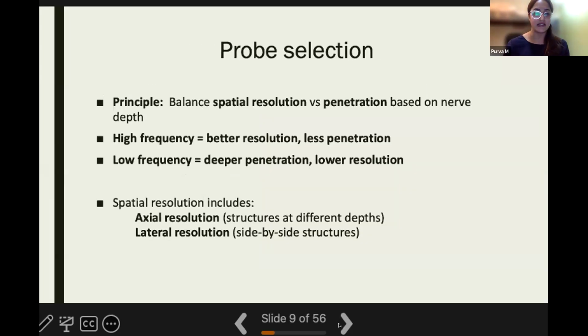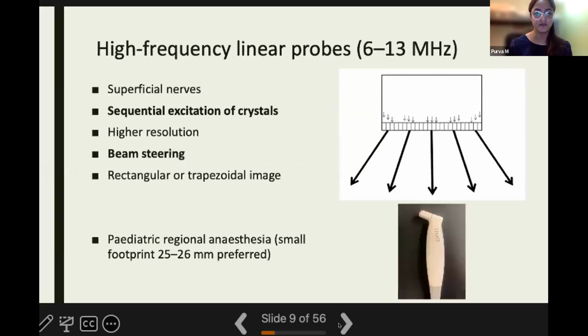So when we are selecting the probe, what are we exactly wanting to achieve? Already it's been discussed, and a lot of stress has been placed on the axial and the lateral resolution. So the whole idea while we are choosing our probes is, if you're choosing a high frequency probe for a superficial structure, we are basically improving our axial and our lateral resolution while trading off penetration. While if we're choosing a low frequency probe, we are getting a deeper penetration but a lower resolution.